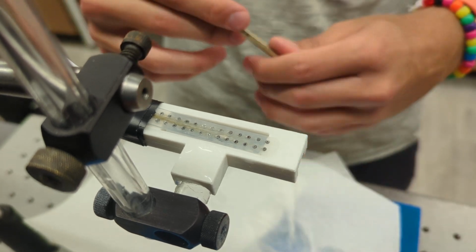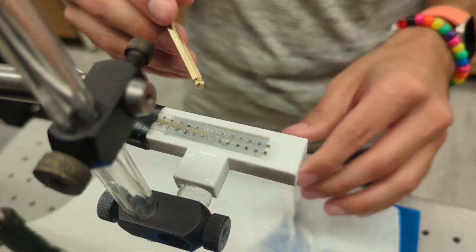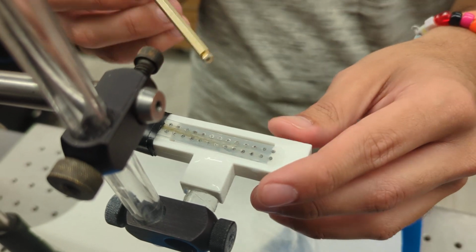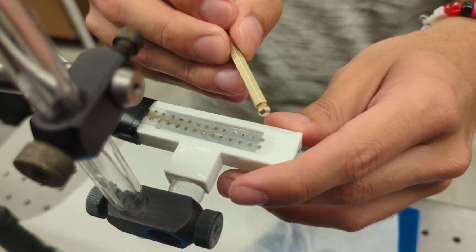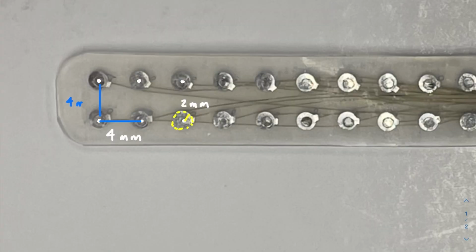In the case of the electrodes used for the experiments, there are multiple electrodes, also known as sites, encased in one plastic substrate. Geometry for our analysis refers to the center-to-center distance between sites and also the diameter of a site. The distance between centers of an electrode site is 4 millimeters, whereas the outside diameter, or the diameter of a whole site, is 2 millimeters.